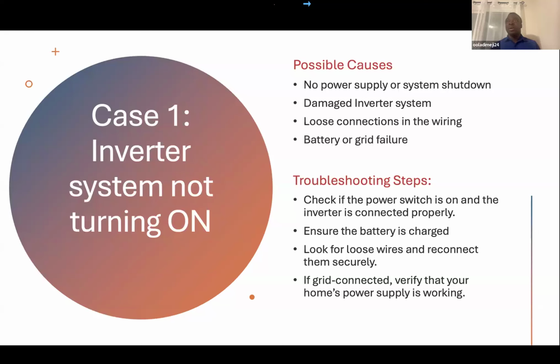First, if a system is not powering on, don't jump to the hardest parts. I see people do this a lot, and it wastes time and it wastes money. What you think is complicated might just have a simple solution. As simple as it is, first check the power switch. Is the inverter on? Are those breakers that are supposed to be on, are they on? Before you start bringing down all the installations, you check the simple things first. Is the inverter powered on? You can never say someone can't just go there and turn it off. It happens sometimes.